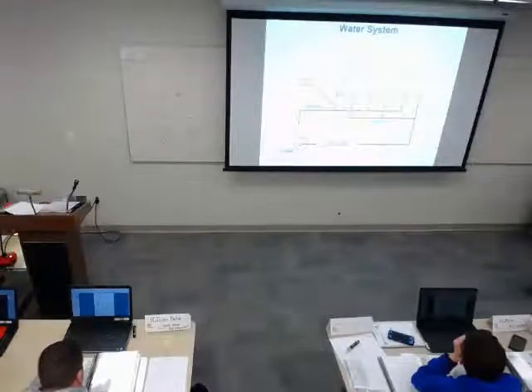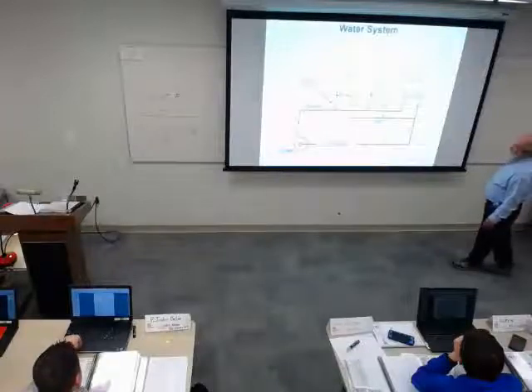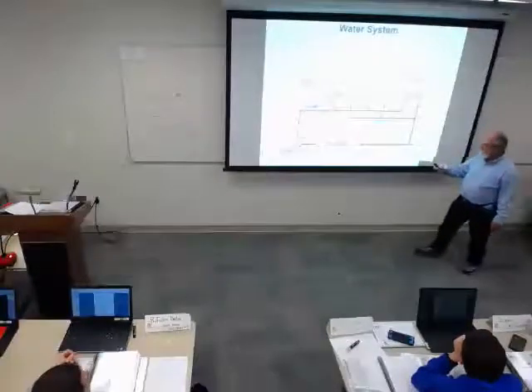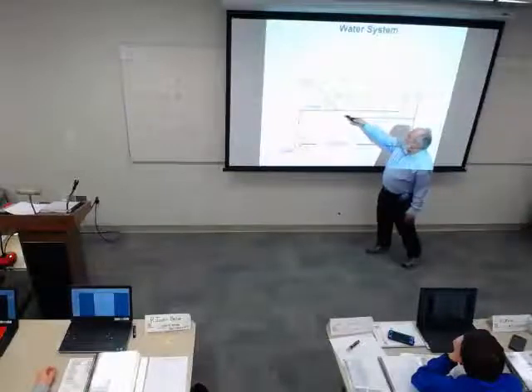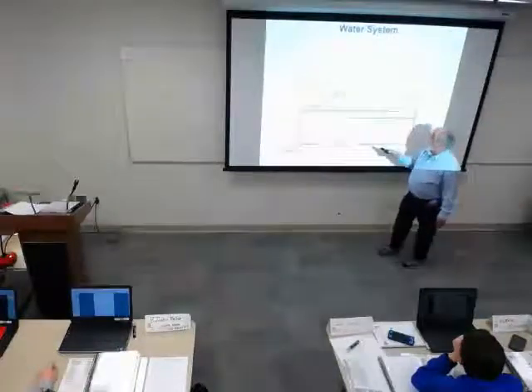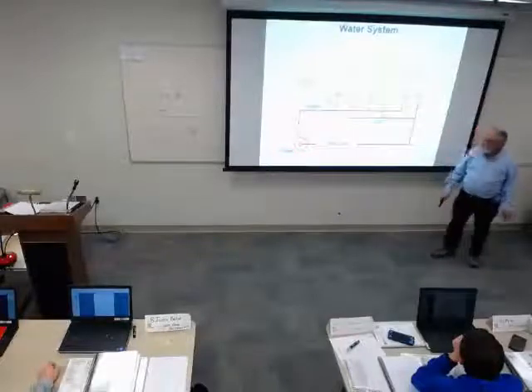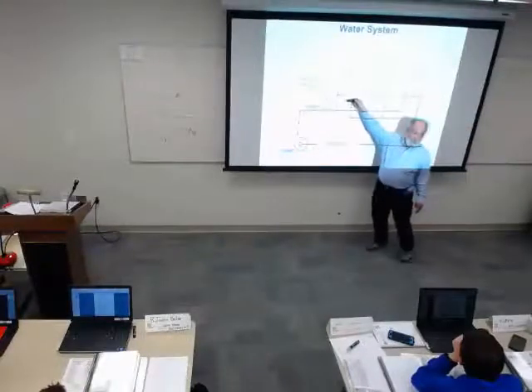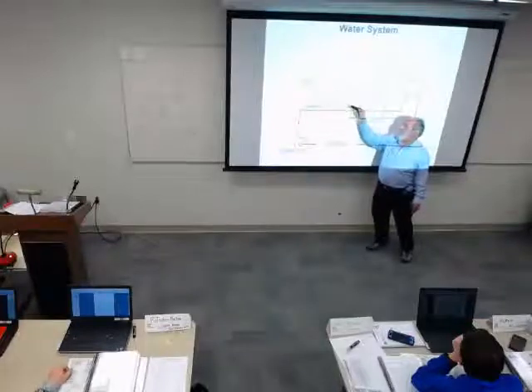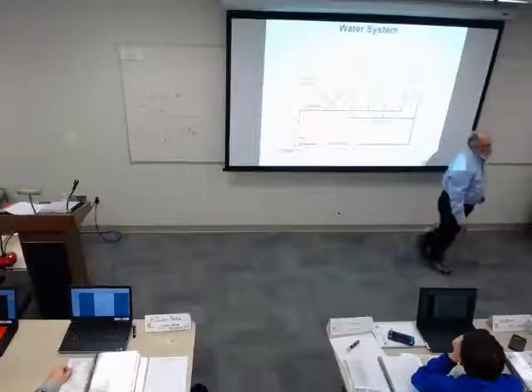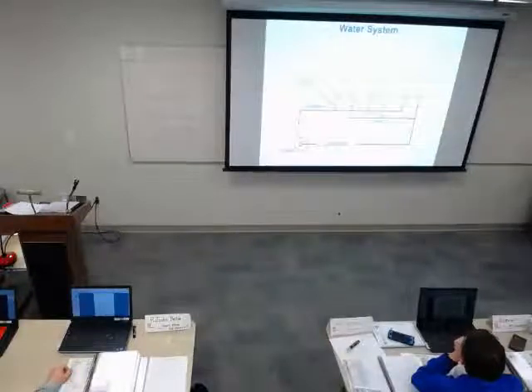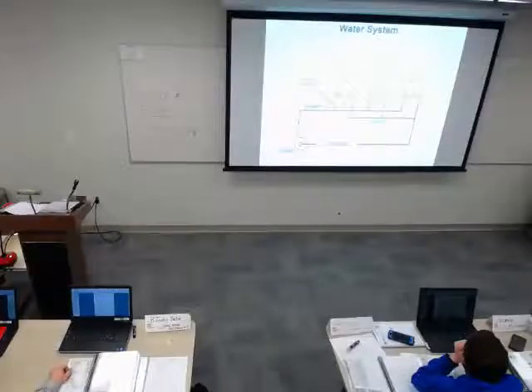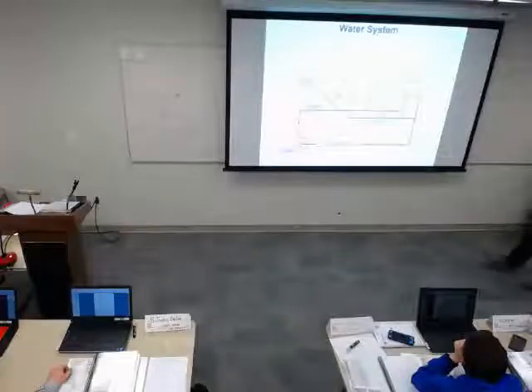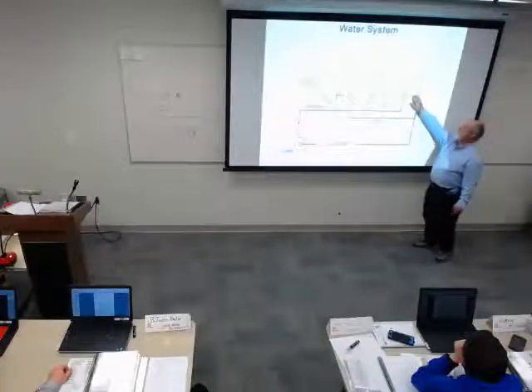So here's a water system. We're going to start with a pump, and we flow out to the system. We've got balance valves. We're showing them here on what looks like the supply side. This particular one has what they call three-way valves, a valve with a bypass. So water's either going through the coil or past the coil or a combination. We don't see a lot of those anymore because we're running more and more to variable pumping systems. So we usually have maybe one or two of those three-way valves in the system, but the rest of the valves are almost always two-way valves, which on the drawing looks like a three-way valve, except this leg is missing.